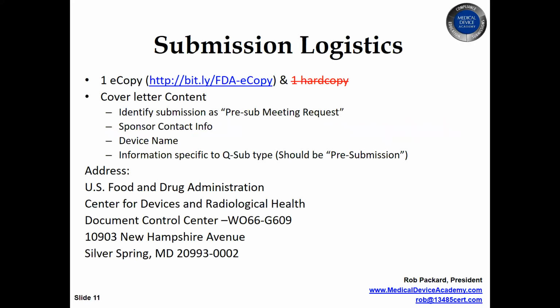So the logistics. I have redlined something here. It says one hard copy. Unofficially, just a few weeks ago, the FDA announced when they had that government shutdown for a whole day, they announced that no longer would you have to submit a full hard copy of your submission whenever you submit. That's both 510Ks, de novos, and pre-subs. You only have to submit a hard copy of the cover letter and the e-copy. So if you're using a flash drive or a CD, you'd submit that plus the cover letter. If you have a two-page cover letter, like most of mine are, or sometimes even one for pre-subs, you're submitting one or two pages of paper plus an e-copy. You don't need a binder anymore.